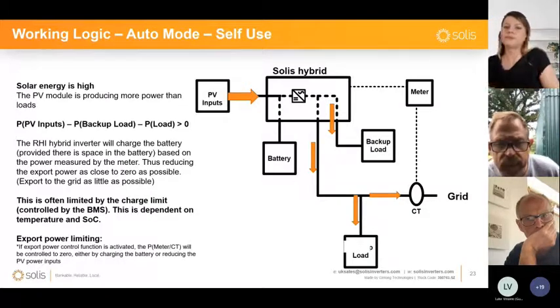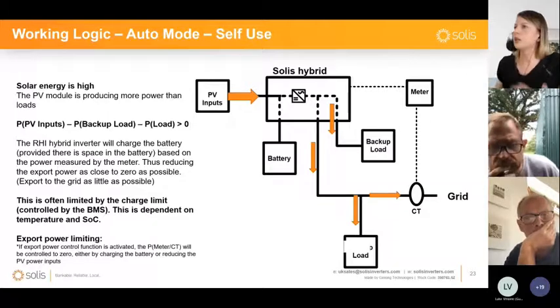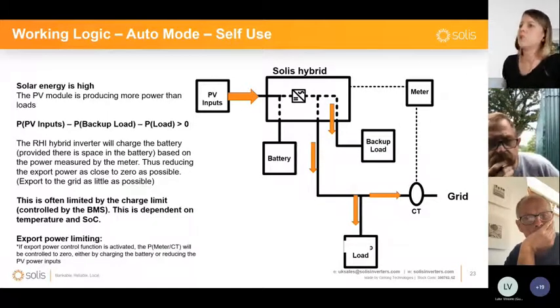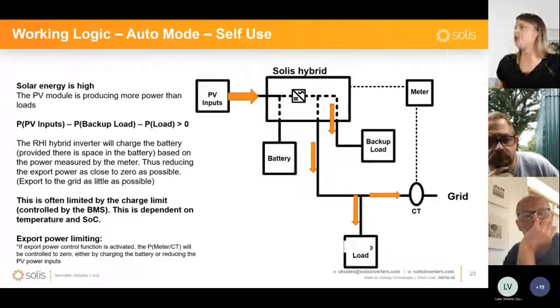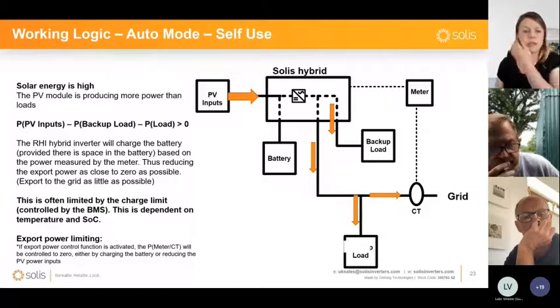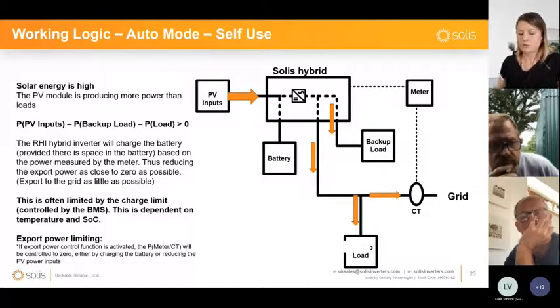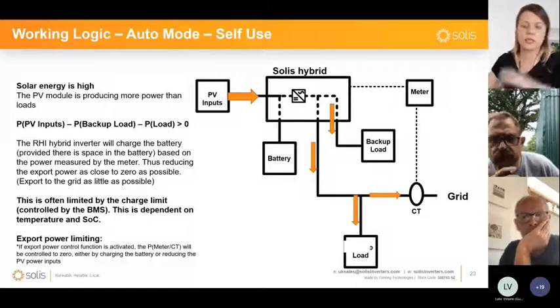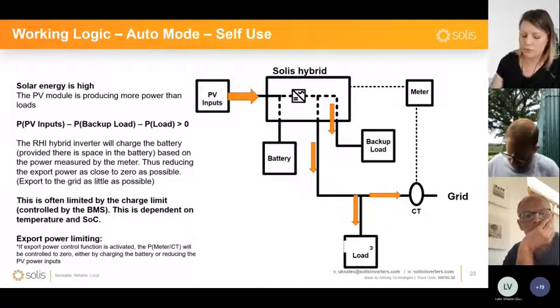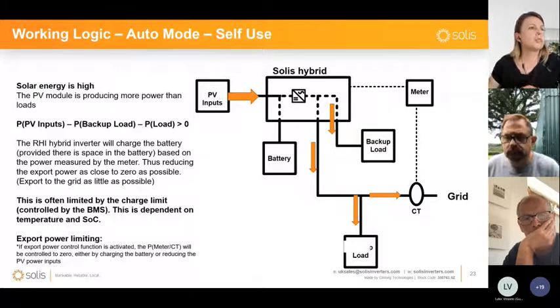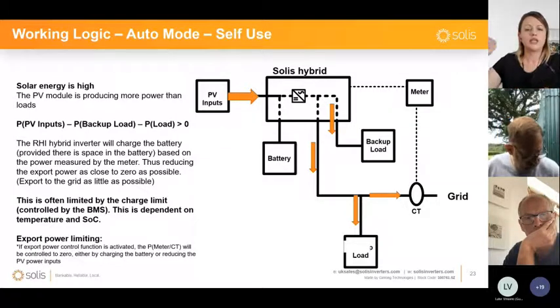So again, we're just going to go a bit through these. The logic of the auto mode, or the self-use mode, is that when the PV is generating more than what the house is consuming, instead of injecting that energy into the grid, it's going to be pushed into the battery if there is enough space available, if the battery is not full yet. Or in some cases, it depends on the battery management system, which is third-party software provided, of course, by the battery manufacturer, and which is able to set some limits for charging and discharging currents.